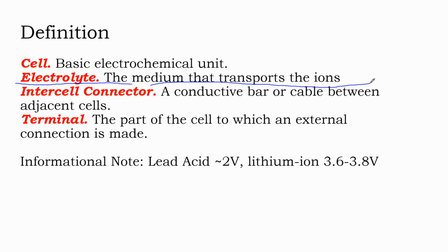But if you work that battery hard enough, with a small battery and a very high charge or discharge rate, you can start getting ripples and bubbling in that electrolyte, and it can actually result in power quality degradation issues, where very sensitive devices might detect that agitation in that battery.